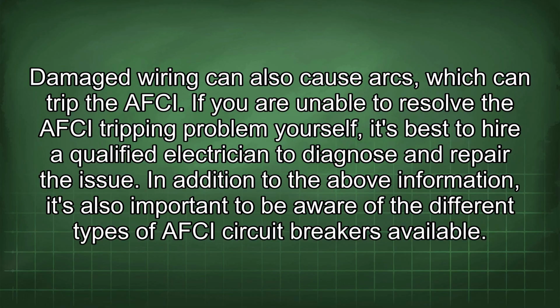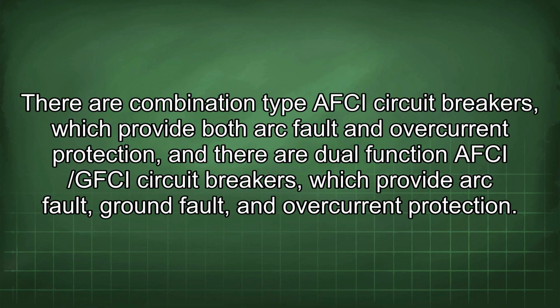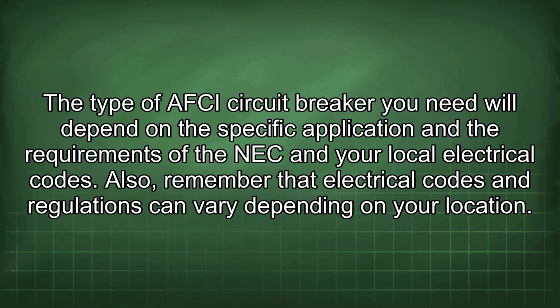In addition to the above information, it's also important to be aware of the different types of AFCI circuit breakers available. There are combination type AFCI circuit breakers, which provide both arc fault and overcurrent protection, and there are dual function AFCI/GFCI circuit breakers, which provide arc fault, ground fault, and overcurrent protection. The type of AFCI circuit breaker you need will depend on the specific application and the requirements of the NEC and your local electrical codes.